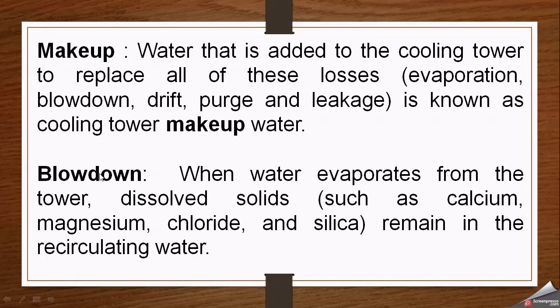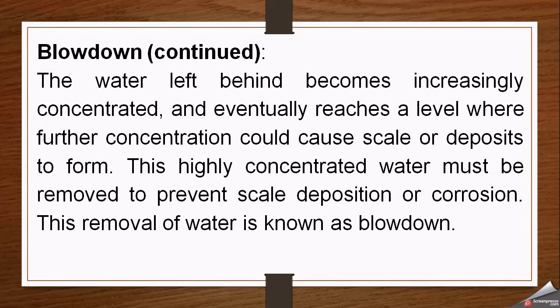Another important term is blowdown. When water evaporates from the tower, dissolved solids such as calcium, magnesium, chloride, silica, and other dissolved solids remain in the recirculating water, because when water evaporates these solids cannot leave with the evaporated water and are left behind.